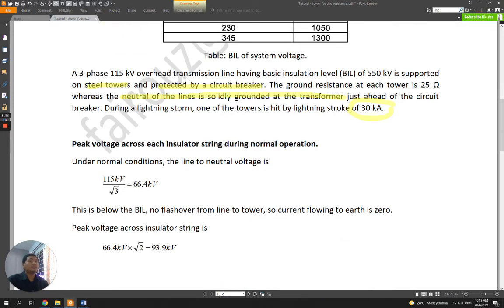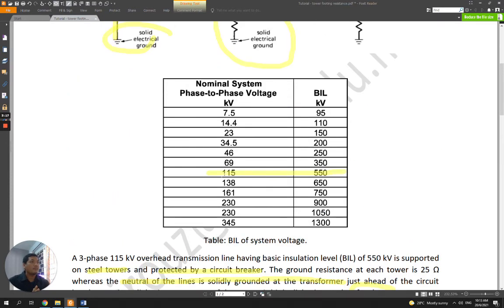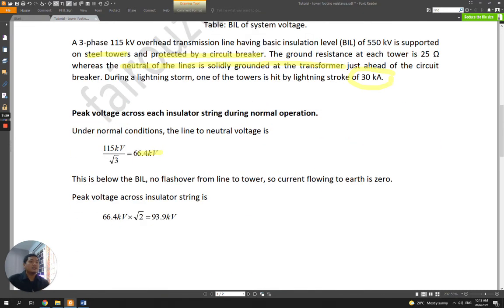So during normal operation, what is the peak voltage across each insulator string? You know that the line to line voltage, or phase to phase voltage, is given, which is 115 kilovolt. So line to neutral is simply 115 kilovolt divided by square root of 3, which is 66.4 kV. So this is the line to neutral voltage or phase voltage. We can see that during normal operation, the voltage across the insulator is only 66.4 kV. This is below BIL.